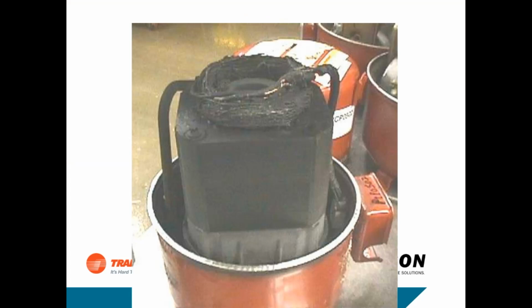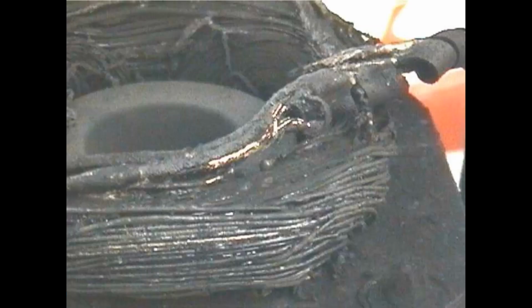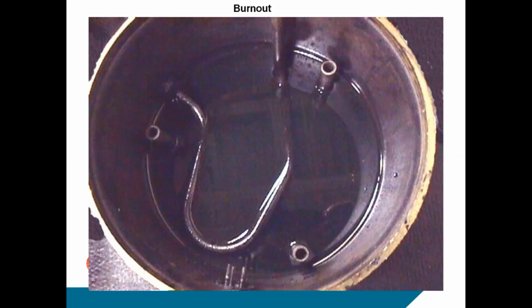So you can imagine if you have electrical problems with a compressor, all this crap is going to be in the system. It's going to be in the oil. It's going to be in the refrigerant. It's going to be out in the system. So if you can catch a compressor problem early before it gets to this point, you can save yourself an awful lot of cleanup time. Again, another close-up of that. That's what the oil looks like. It looks like black gold when it's burned out.